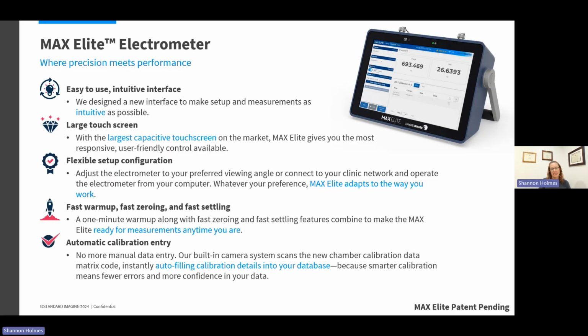We've also implemented a data matrix reader so that you can automatically read in the calibration data info for your chambers, so that it'll autofill the calibration details, so that you are less likely to have to deal with manual data entry errors. You can actually have confidence in the values that are entered into the data library. I did forget to mention we do have a patent pending on this device.